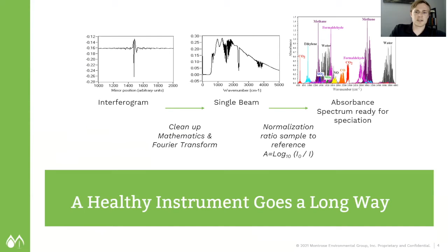So on the screen to the right, you can see most of the analytes of interest, like formaldehyde, methane, certain gases, aren't going to be as affected by an unhealthy instrument. You'll still be able to collect good data for the most part. But if you're looking at really low level detections, parts per billion detections, or things that are what we call sticky, or that react to temperatures much more readily, your formaldehyde, ammonia, SO2, acid gases, things along those lines, your instrument needs to be in really good shape, because you can't claim ultra low detection and have a poor instrument. It doesn't work.